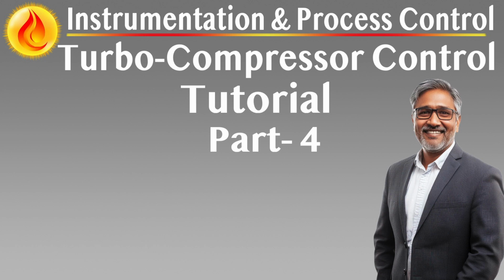Suppression system control and monitoring. The TCCS monitors the health, readiness, and actuation status of water mist or CO2 suppression systems. Visual and audible alerts are generated locally on the Unit Control Panel, UCP, HMI, and remotely on the Distributed Control System, DCS. Shutdown coordination. On fire or gas detection, the TCCS executes a controlled turbine shutdown, coordinates with the Emergency Shutdown System, ESD, and activates permissives and sequencing for safe depressurization and blowdown, if configured.